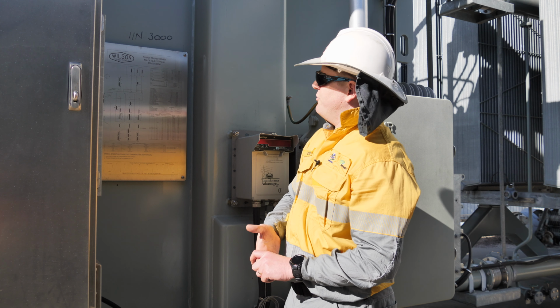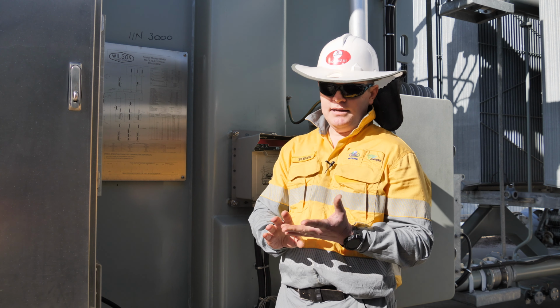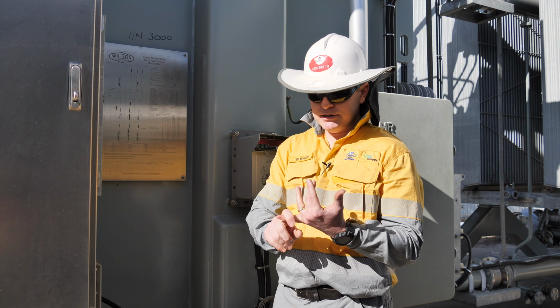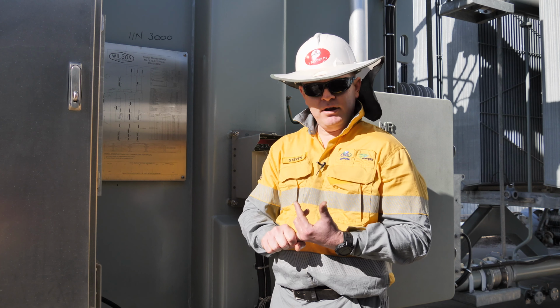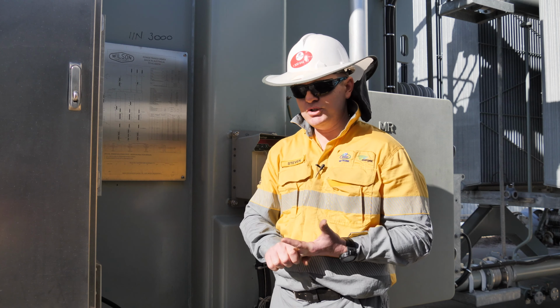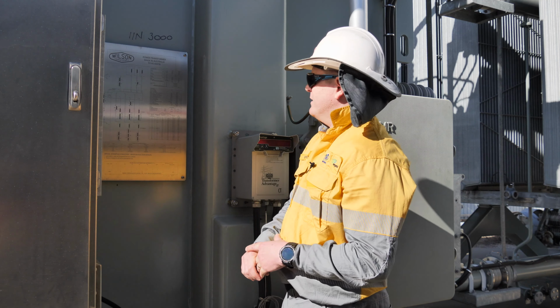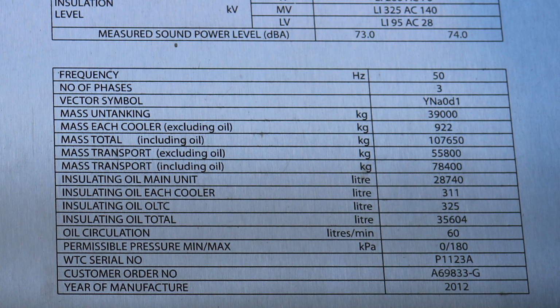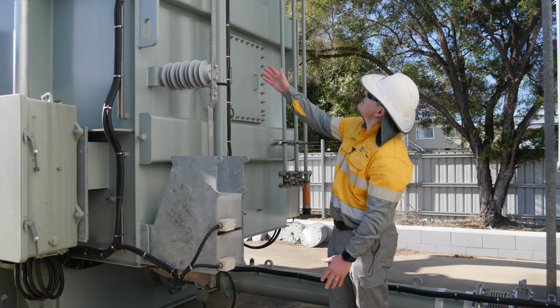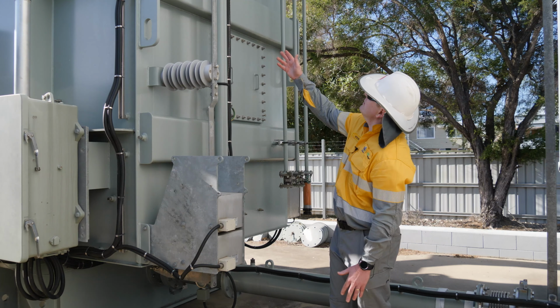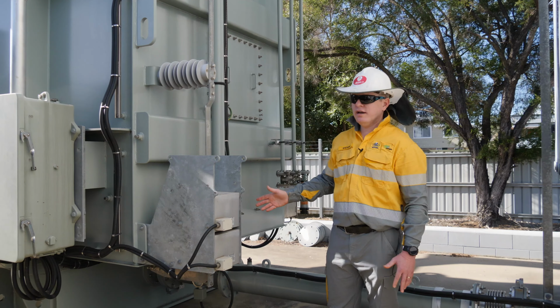Now this transformer actually has 3 windings. It's got a primary winding at 132 kV, secondary at 66, and a tertiary at 11. And the vector grouping for this particular transformer is YNa0d1. So this system we see here, this is actually the neutral earthing system of the transformer.